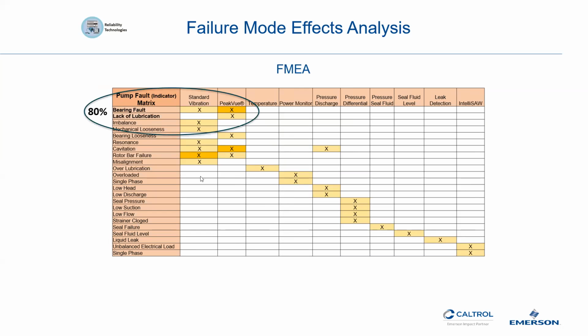We find that 80% of failures in the pumps are happening either from a bearing fault, lack of lubrication, imbalance, or mechanical looseness. Those are the top candidates, and vibration analysis targets that. And we'll talk about PeakVue. That's a bearing technology, and we'll talk about that a little bit later here in the PowerPoint.